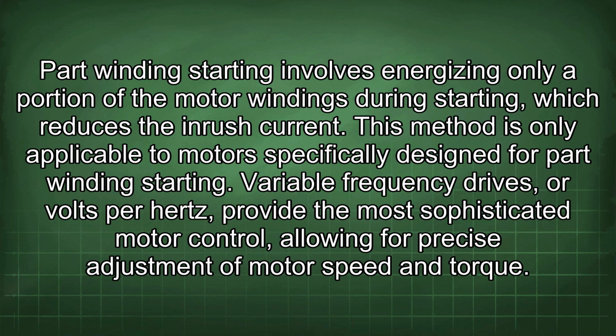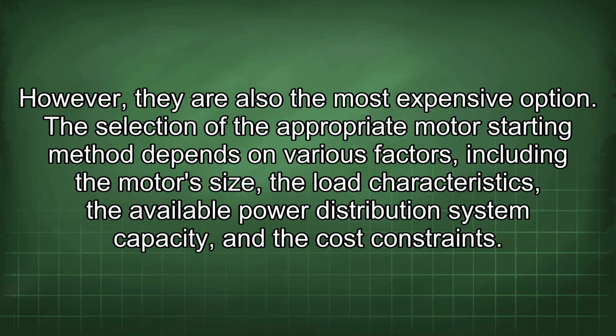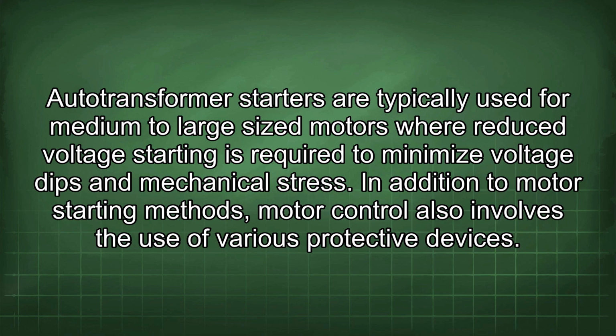Variable frequency drives, or volts per hertz, provide the most sophisticated motor control, allowing for precise adjustment of motor speed and torque. However, they are also the most expensive option. The selection of the appropriate motor starting method depends on various factors, including the motor's size, the load characteristics, the available power distribution system capacity, and the cost constraints. Autotransformer starters are typically used for medium to large size motors where reduced voltage starting is required to minimize voltage dips and mechanical stress. In addition to motor starting methods, motor control also involves the use of various protective devices.